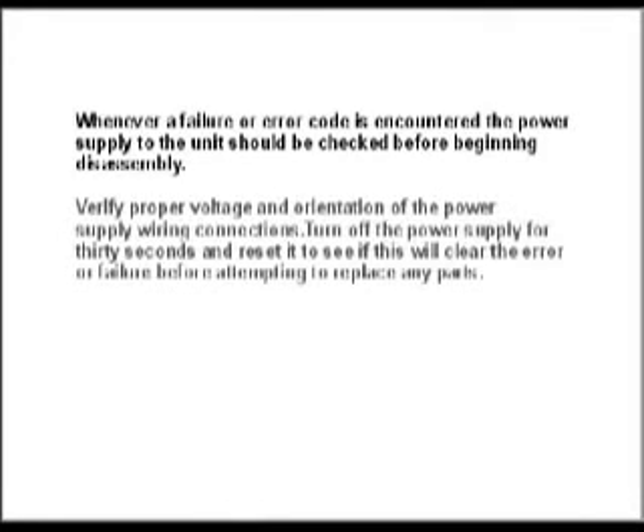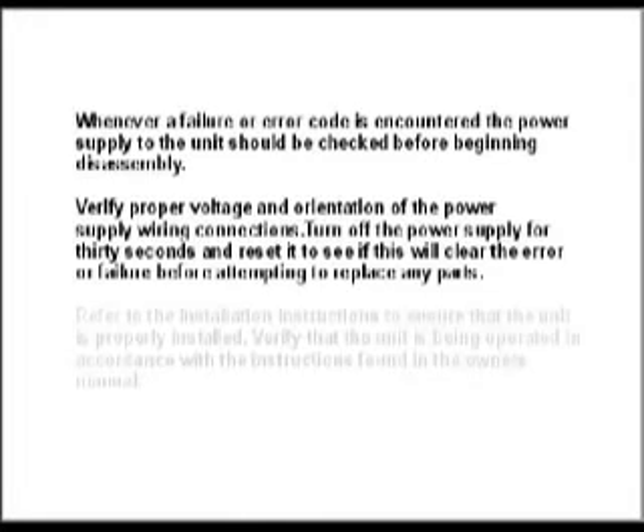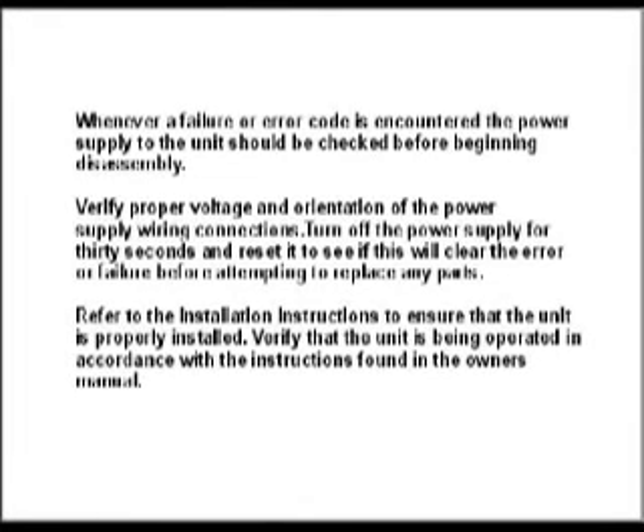Whenever a failure or error code is encountered, the power supply to the unit should be checked before beginning disassembly. Verify proper voltage and orientation of the power supply wiring connections. Turn off the power supply for 30 seconds and reset it to see if this will clear the error or failure before attempting to replace any parts. Refer to the installation instructions to ensure that the unit is properly installed. Verify that the unit is being operated in accordance with the instructions found in the owner's manual.